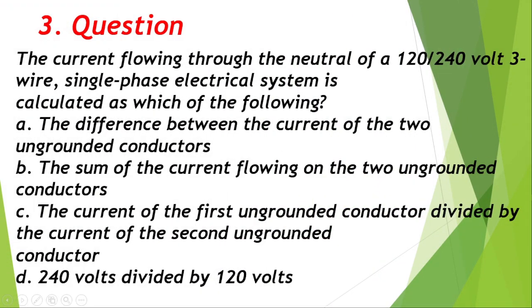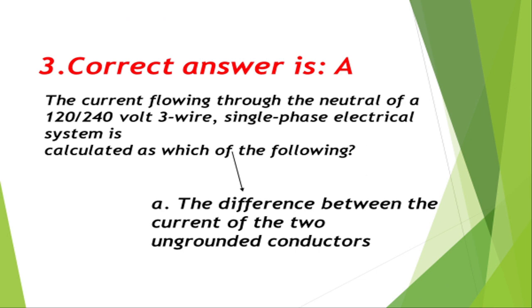Question number 3: The current flowing through the neutral of a 120/240-volt three-wire single-phase electrical system is calculated as which of the following? A. The difference between the current of the two ungrounded conductors, B. The sum of the current flowing on the two ungrounded conductors, C. The current of the first ungrounded conductor divided by the current of the second, D. 240 volts divided by 120 volts. Correct answer is A, the difference between the current of the two ungrounded conductors.